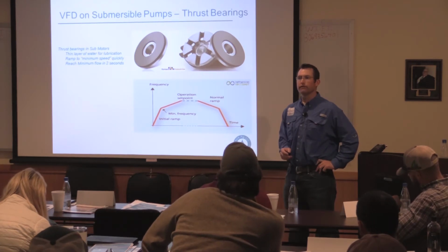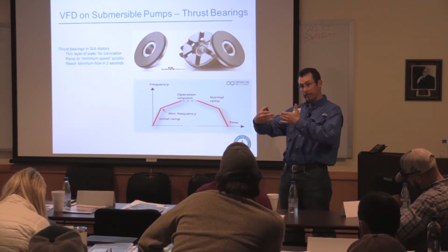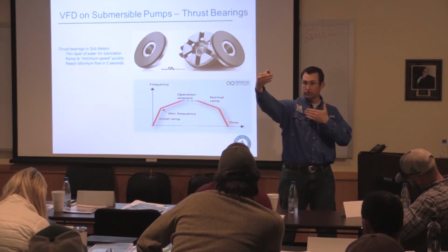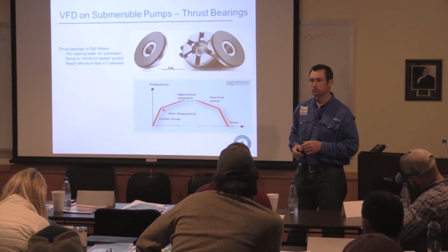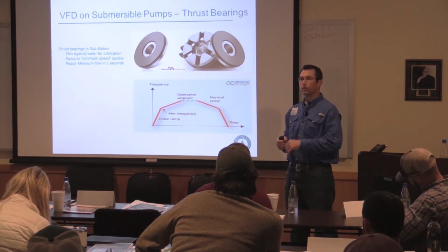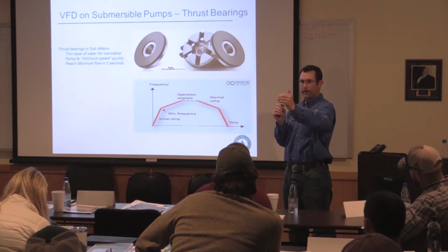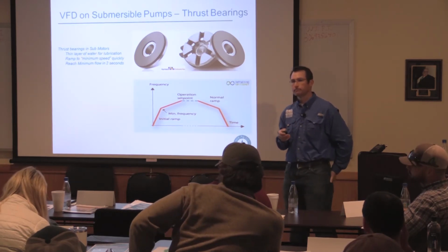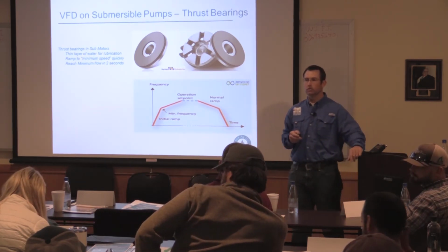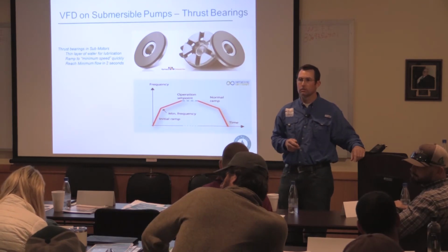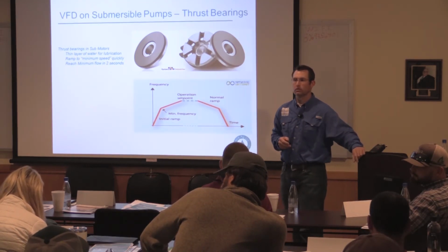Where's your drive located? So is your drive located at the genset and your pump's a ways away? Yes, at the top. It's at the pump. Okay, but you're running the power to the bottom of the hole, which is 600 feet. Yeah. So everything that we're doing now is anything over 400 feet has to have a load reactor on it.